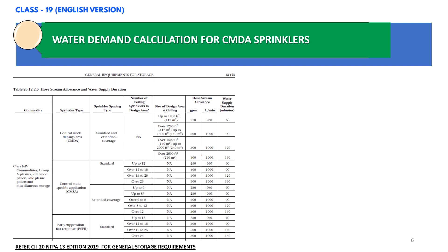We have already determined the actual density based on the storage height, and we know the area of sprinkler operation is 2000 square feet from the previous slide. Now we shall calculate the hose stream allowance and water supply duration. From table 20.12.2.6 in NFPA 13 2019 edition, since we have Class 4 commodity and are using CMDA sprinklers with an area of sprinkler operation of 2000 square feet, the required hose stream allowance will be 500 gpm and the water supply duration will be 120 minutes.